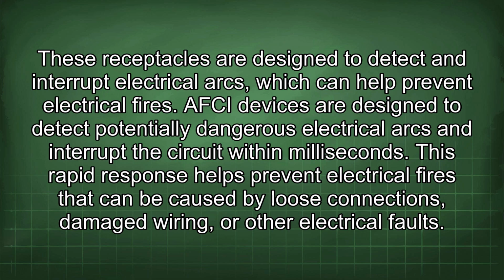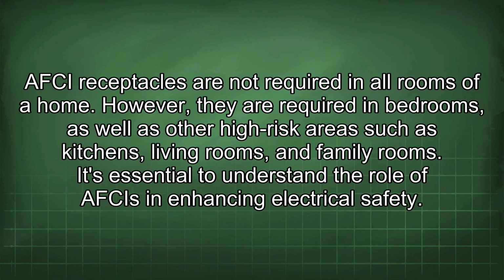AFCI devices are designed to detect potentially dangerous electrical arcs and interrupt the circuit within milliseconds. This rapid response helps prevent electrical fires that can be caused by loose connections, damaged wiring, or other electrical faults. AFCI receptacles are not required in all rooms of a home. However, they are required in bedrooms as well as other high-risk areas such as kitchens, living rooms, and family rooms. It's essential to understand the role of AFCIs in enhancing electrical safety.